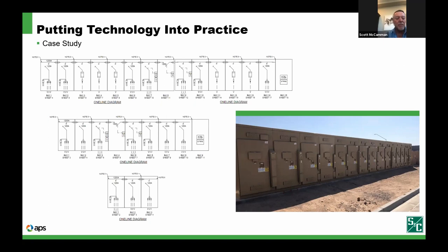The reason we ended up adding the 9 and the 3-bay was to be able to handle the loads, at least the temporary loads for the second customer, but also the third customer was coming in, and that third customer was planned to share the same feeder as the first customer. We had no switching abilities for that first feeder, and so we had to install the 9-bay and the 3-bay. We took the temporary feeder into the 9-bay, then over to the 3-bay, and then over to the second customer. Out of that 3-bay, we backfed the first customer. The 9-bay had an AT switch, so we took advantage of that.